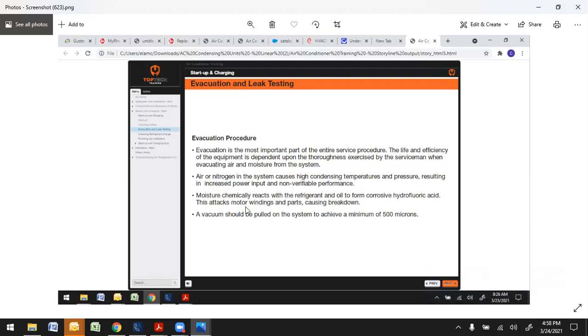Another thing is moisture will chemically react with refrigerant and oil to form a corrosive hydrofluoric acid. This attacks the motor windings and parts, causing breakdown. This doesn't take place immediately. This takes place 4, 5, 6, 7 years down the road, and that's when you start losing a compressor. A vacuum should be pulled to a minimum of 500 microns.